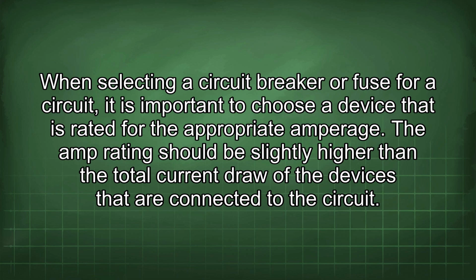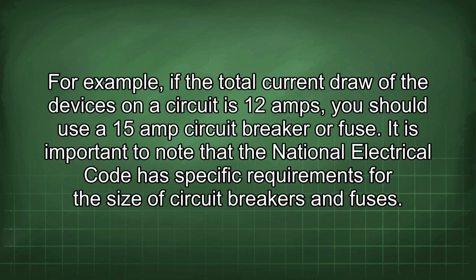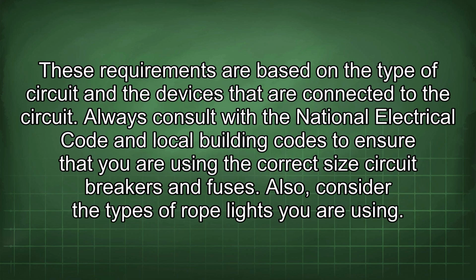The amp rating should be slightly higher than the total current draw of the devices that are connected to the circuit. For example, if the total current draw of the devices on a circuit is 12 amps, you should use a 15 amp circuit breaker or fuse. It is important to note that the National Electrical Code has specific requirements for the size of circuit breakers and fuses. These requirements are based on the type of circuit and the devices that are connected to the circuit. Always consult with the National Electrical Code and local building codes to ensure that you are using the correct size circuit breakers and fuses. Also, consider the types of rope lights you are using.